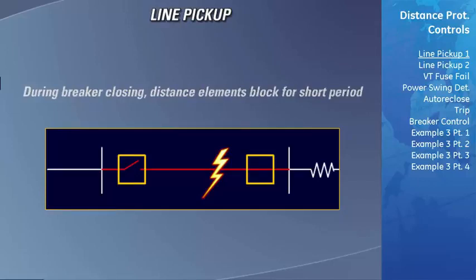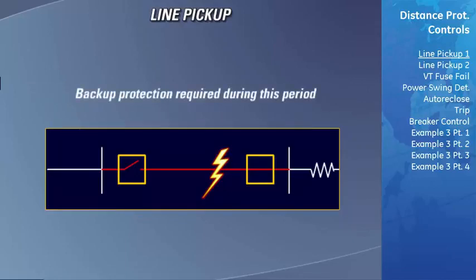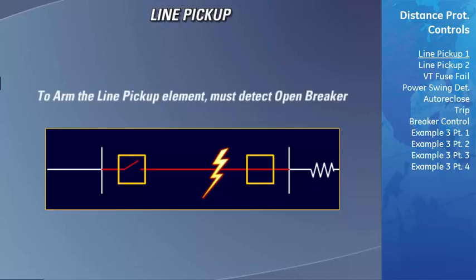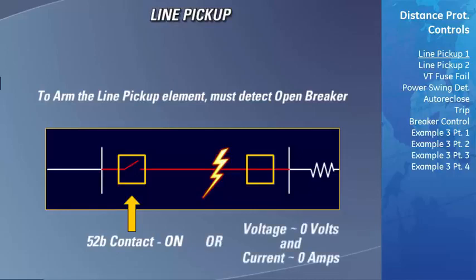Before the line pickup protection element will be made available to protect the transmission line, it must first detect that the breaker leading into the transmission line is open. This is sometimes known as arming the line pickup element. There are two ways that the line pickup element can detect if the breaker leading into the transmission line is open. The first is by reading the status of the breaker 52B contact. If the 52B contact is wired to a contact input of the D60 and that contact input is forced on, it means that the breaker is open. The other way the element detects an open breaker is by detecting that the magnitude of the current and the magnitude of the voltage have both essentially dropped to zero. Either of these conditions will arm the line pickup element.